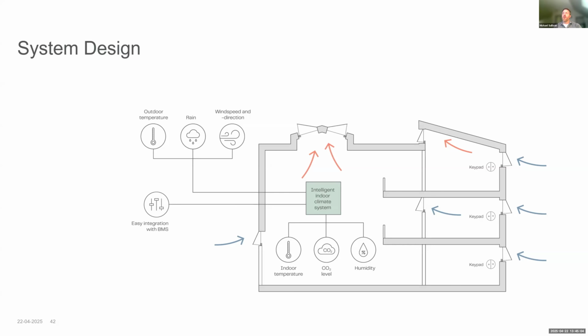As you can see in the middle, it has the intelligent indoor climate system, which is usually going to be the BMS and control panel system for actuators and all of the sensors. With that, we have the indoor temperature sensors, the CO2 sensors, and the humidity controls, which would typically be with the indoor temperature controls. Those you typically want near the windows, but also able to read the entire room that they are based or zoned in, so you can have that indoor-outdoor comparison and where we need to regulate the levels.